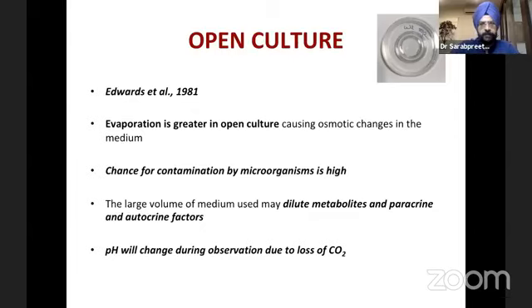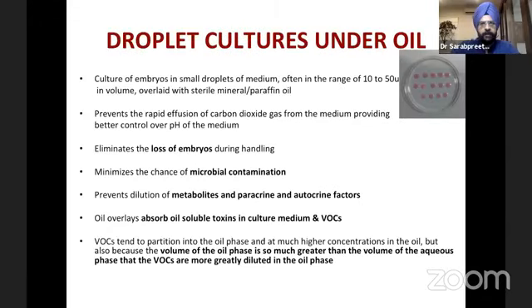Now, this was the open culture dish in which Edwards cultured till 1981. Evaporation is much greater in open culture and the chance of contamination by microorganisms is high. The high volume of medium used may dilute metabolites and paracrine and autocrine factors. And there's a lot of pH change observed due to loss of CO2. So we came up with droplet cultures under oil, in which 10 to 50 microliter droplets of medium are prepared and overlaid with oil. It prevents the rapid effusion of carbon dioxide gas from the media, allowing better control of pH, eliminates the loss of embryos during handling, minimizes microbial contamination, and preserves autocrine and paracrine factors. It also absorbs toxins as well as VOCs.